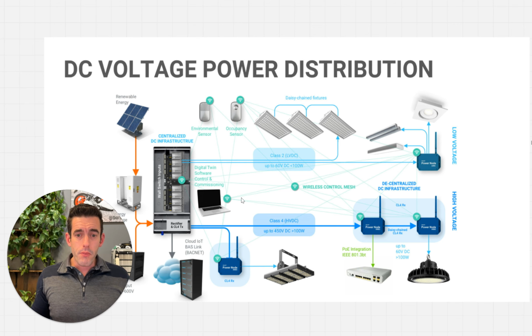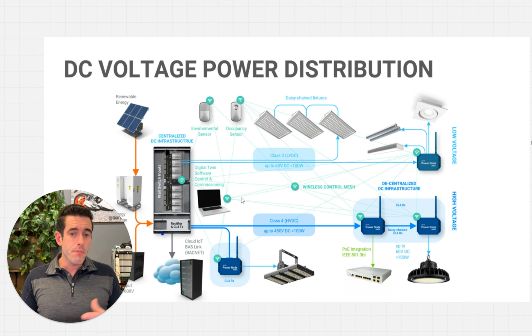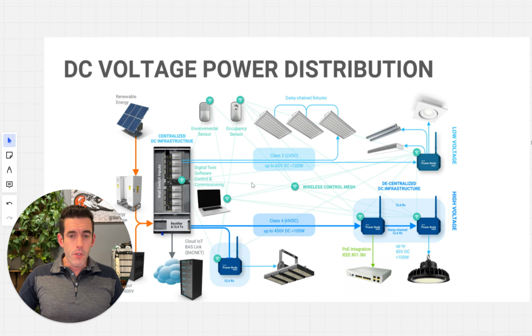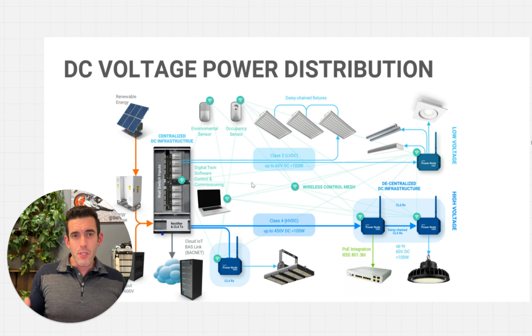There's a broader spectrum to that, but the foundation is it's basically everything that's under 60 volts DC and under 100 to 120 watts. Within that, it's low power devices, relatively shorter distances. You broadly speak within about 200 to 300 feet is about as far as you want to go.